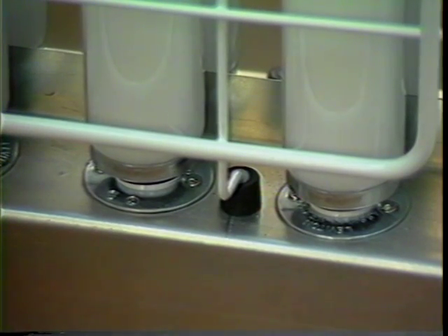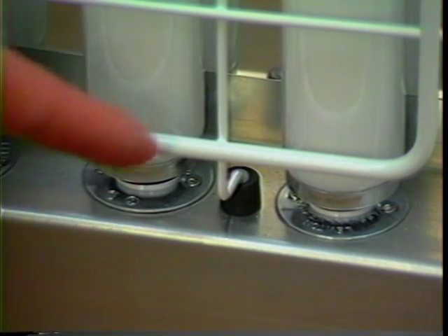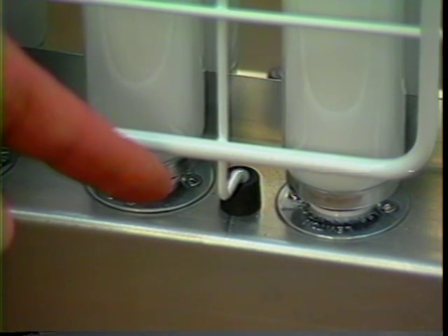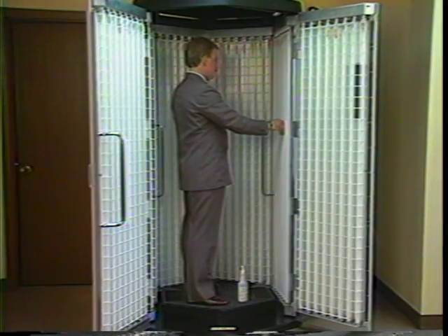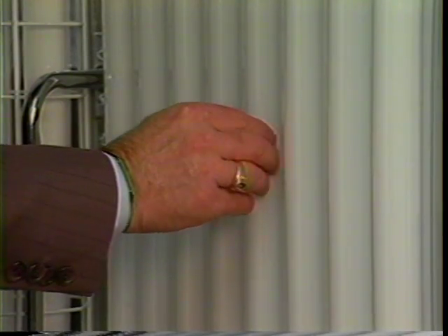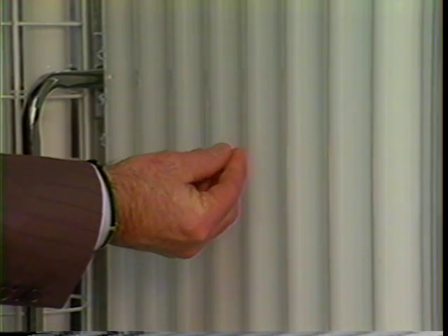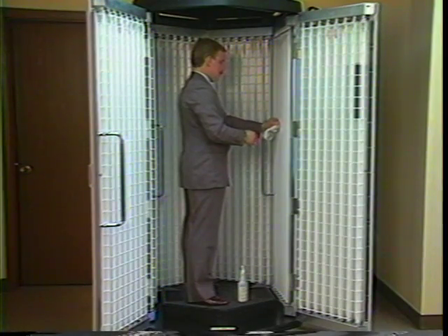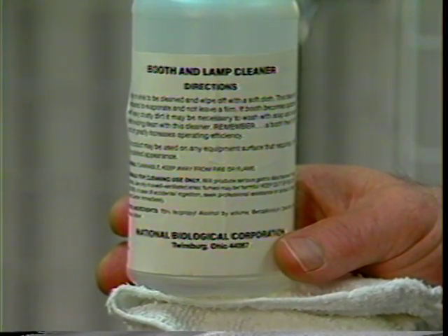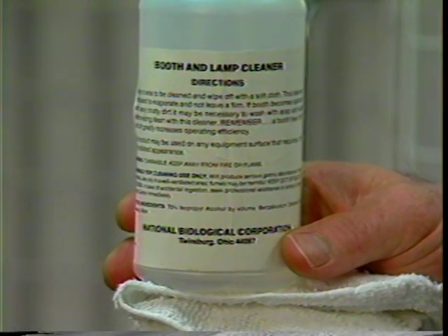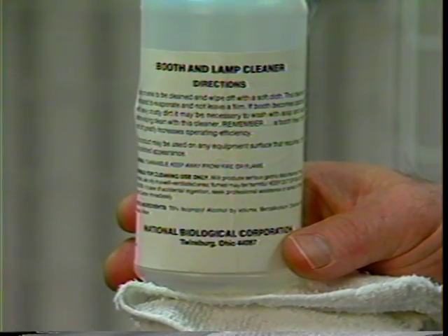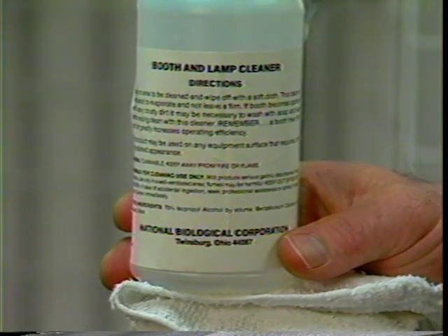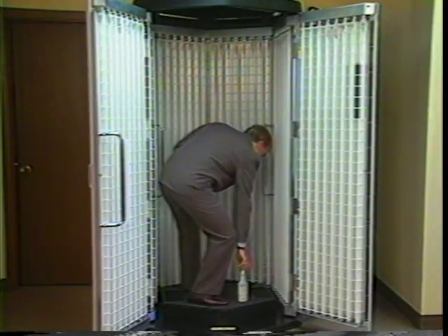Notice the bottom screen tips have small rubber feet which hold the screen at a precise level when attached to the section. The lamps and reflectors are now ready for cleaning. You will know when the lamps need cleaning because a dirty lamp will feel oily to the touch and a clean lamp should squeak when rubbed with the fingers. Use only National Biological lamp and booth cleaner for lamps and reflectors. Other cleaners may leave a film on the lamps and reflectors, which over time will build up to a level that may reduce lamp output.